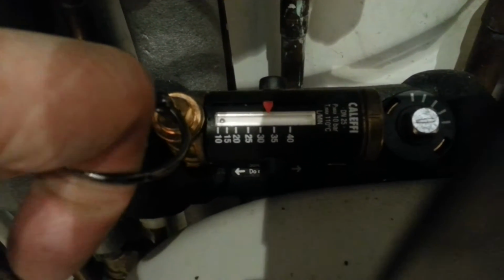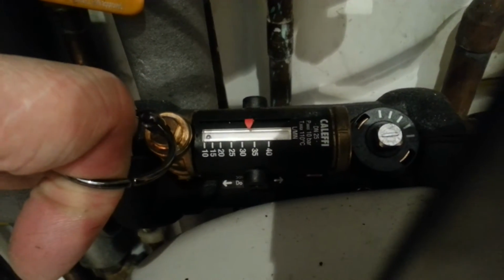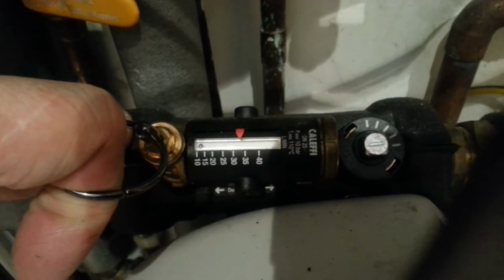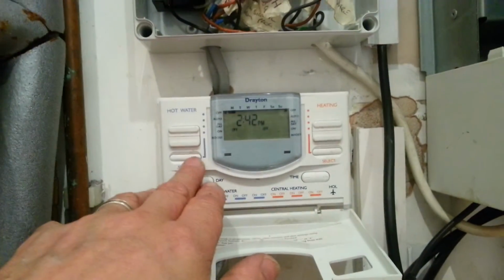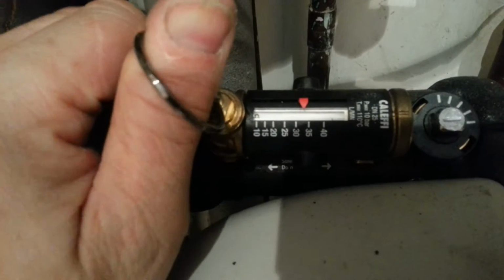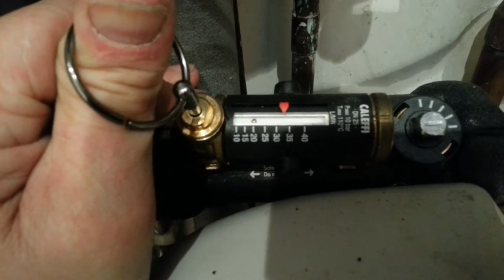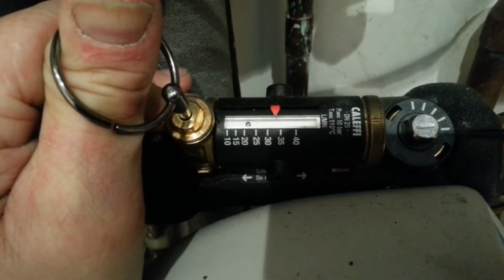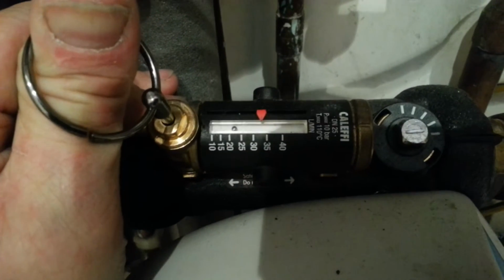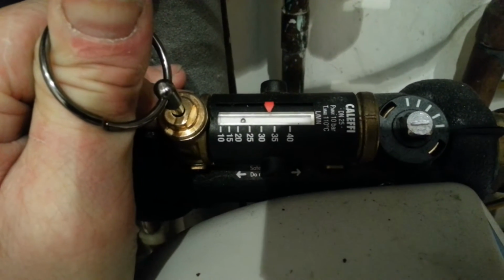At the moment I've got a tiny flow rate through there, only about 12 litres, and if I operate some of the circuits we can see it increase. So if I turn on the hot water, I'll open the hot water valve on one of the cylinders. You can see the flow rate on the second part of the system's gone up. About 22 litres a minute. So you can see that coming on.